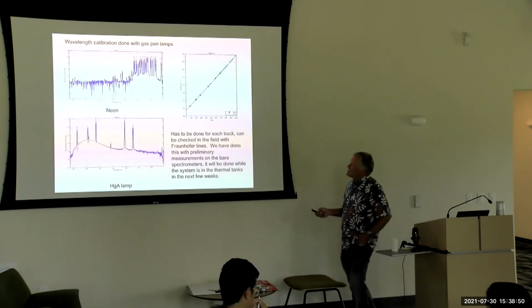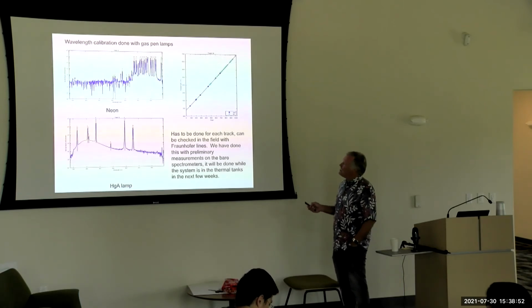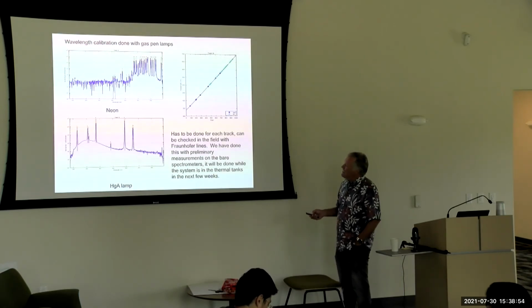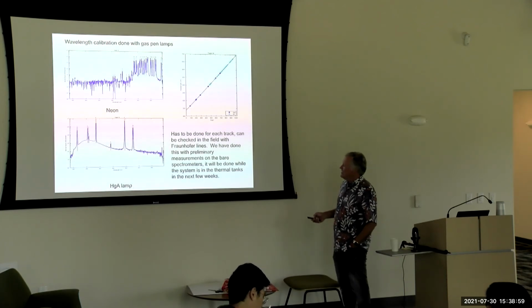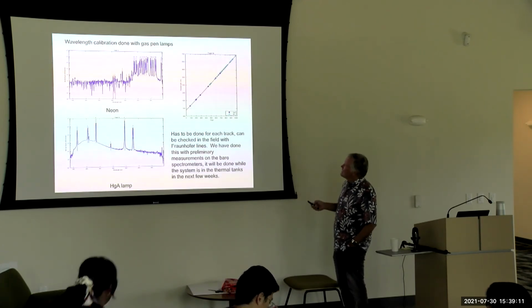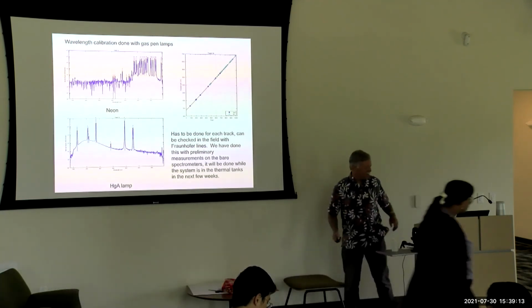Wavelength calibration is done by looking with a gas penlight lamp. This shows a mercury argon lamp and these different spectral lines. You know where these spectral lines are really accurately, so you can change the pixel location to a wavelength and use the calibration for that. Here's a neon lamp.